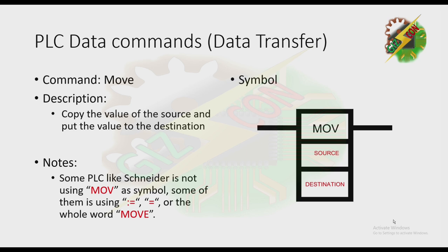Let's discuss data transfer — we have the Move command. The Move command copies the value of the source and puts the value to the destination. Take note that some PLCs like Schneider do not use 'MOV' as the symbol; some use colon-equal or the whole word 'move'. This is the symbol for this command.